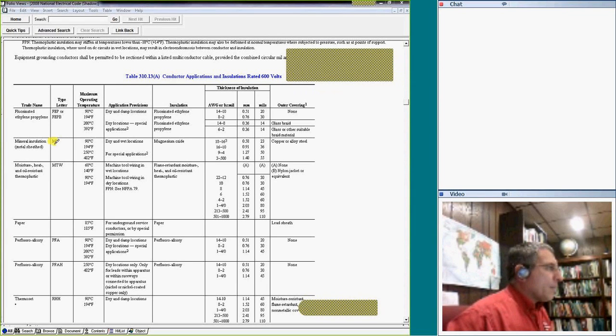Let's start with a cable. If you're using MI cable, if you use it in a dry and wet location, 90 degrees, no problem. With special permission, it can go as high as 250. Okay, MI cable. Check your left. Let's look at RHH. It's thermoset. It's rated for 90 degrees in a dry and damp location.